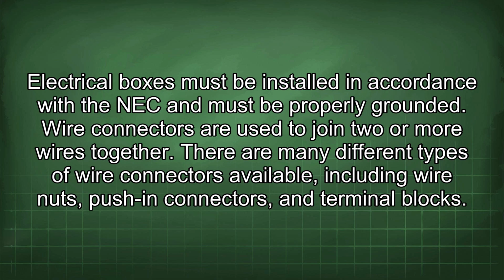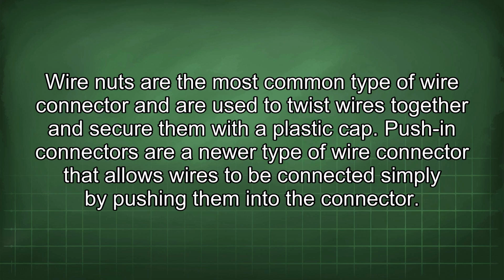Wire connectors are used to join two or more wires together. There are many different types of wire connectors available, including wire nuts, push-in connectors, and terminal blocks. Wire nuts are the most common type of wire connector and are used to twist wires together and secure them with a plastic cap. Push-in connectors are a newer type of wire connector that allows wires to be connected simply by pushing them into the connector.